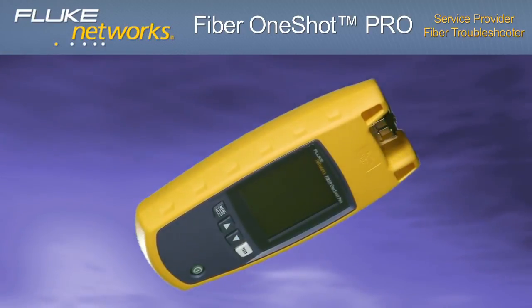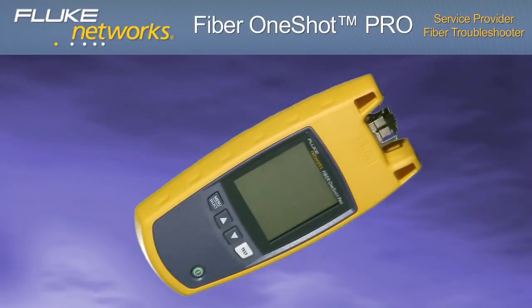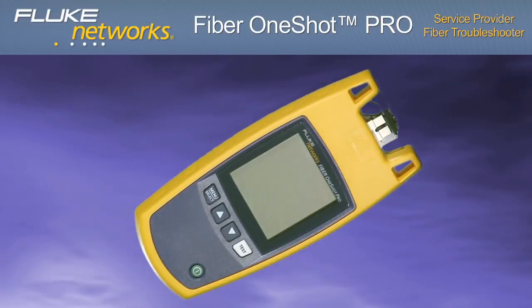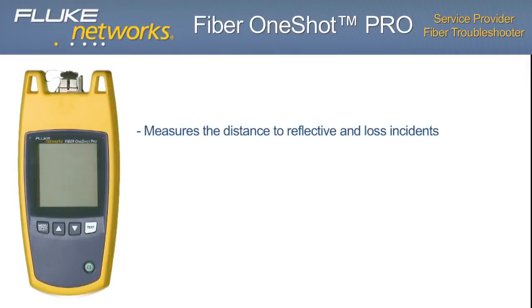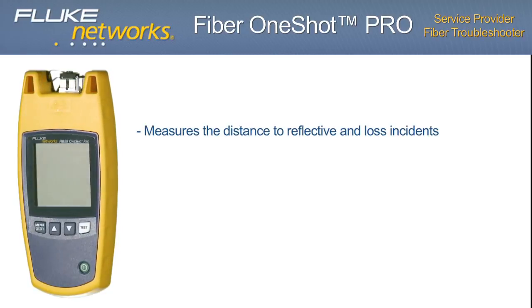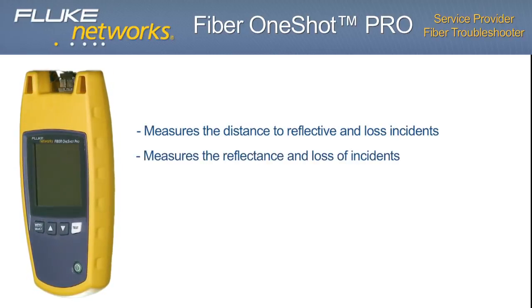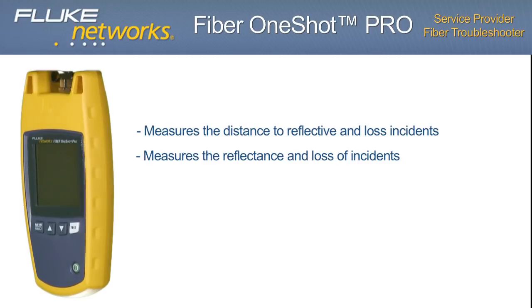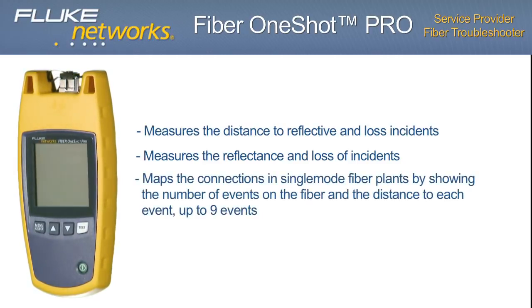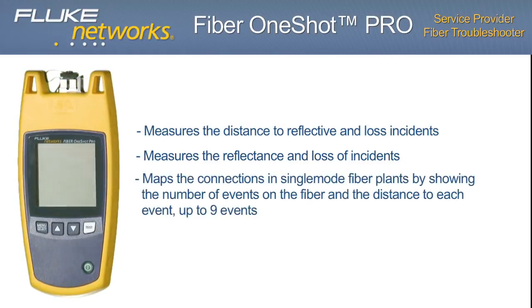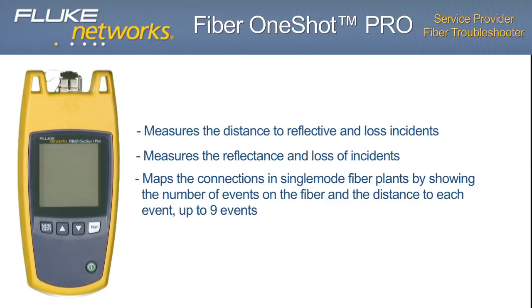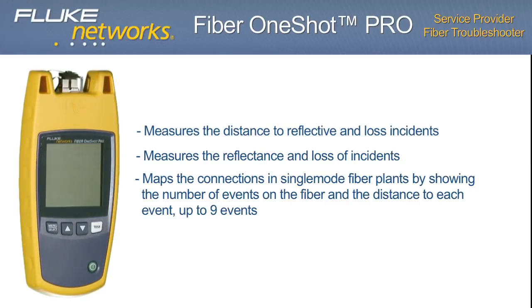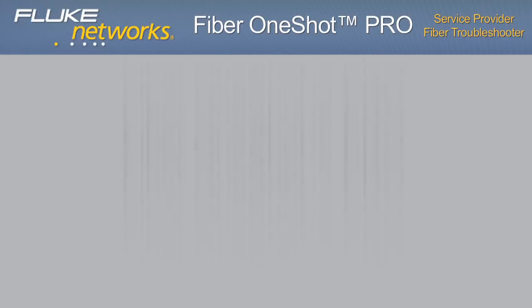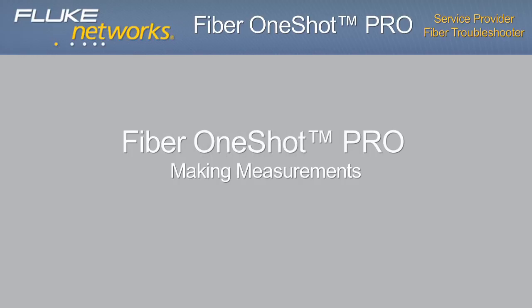The Fiber OneShot PRO performs the following tests to help you find incidents on single-mode fiber optic cables. Measures the distance to reflective and loss incidents. Measures the reflectance and loss of incidents. Maps the connections in single-mode fiber plants by showing the number of events on the fiber and the distance to each event, up to 9 events. Cleaning, adapters, and making measurements.